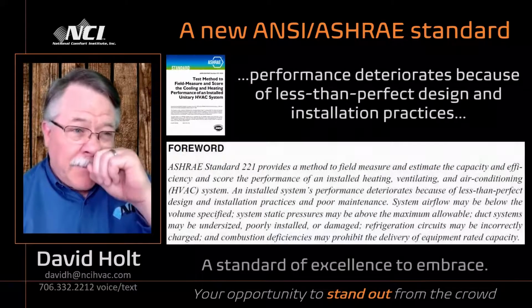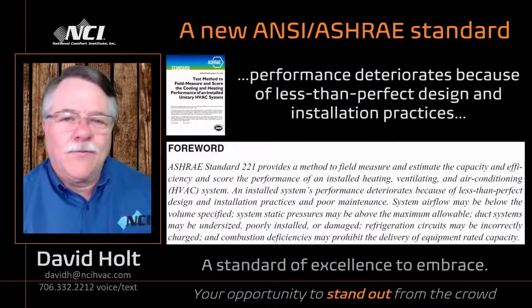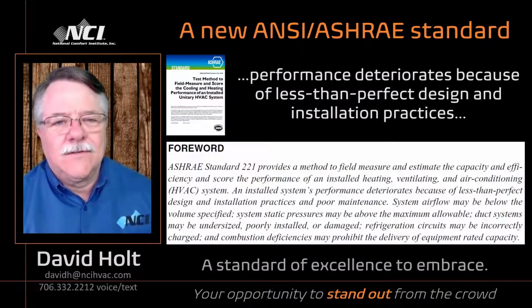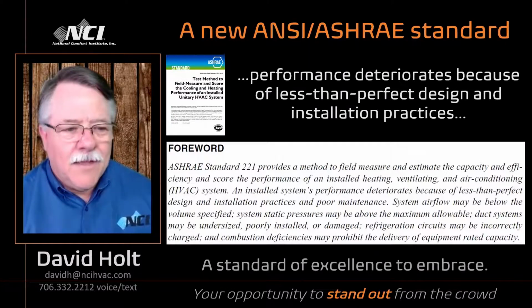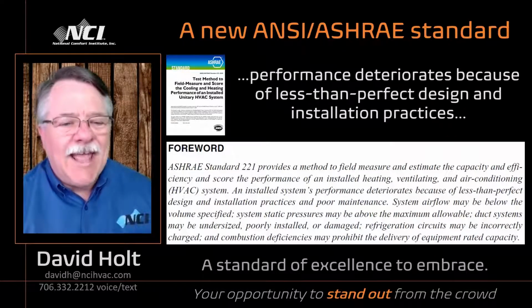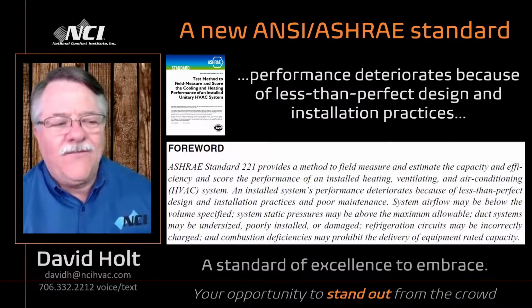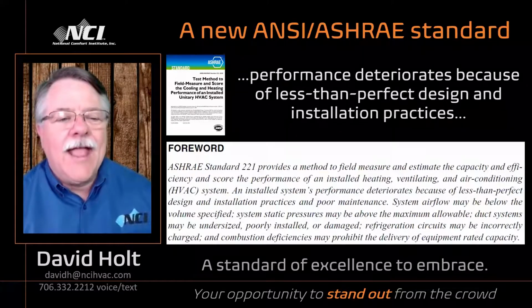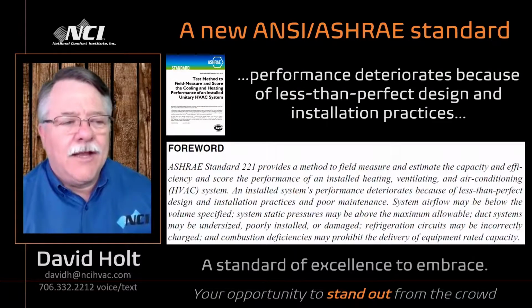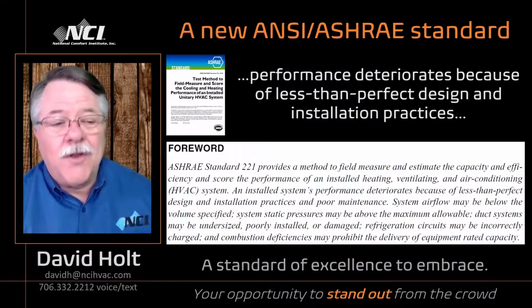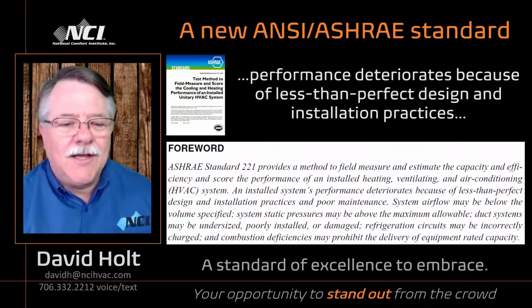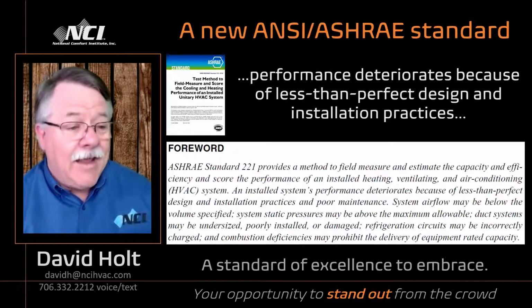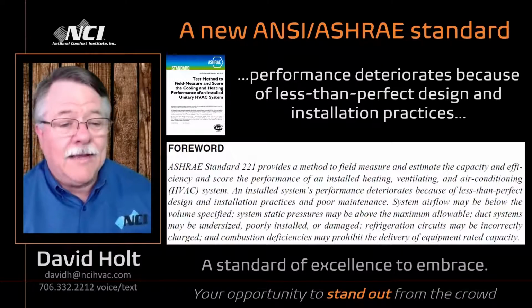Let me show you how. This is the forward, right inside the cover of the standard. It's a full page of text defining a standard of excellence that we as an industry should embrace. It's a method to field measure and estimate the capacity and efficiency, and score the performance of an installed heating, ventilating, and air conditioning system. An installed system's performance deteriorates because of less than perfect design and installation practices and poor maintenance. System airflow may be below the volume specified.